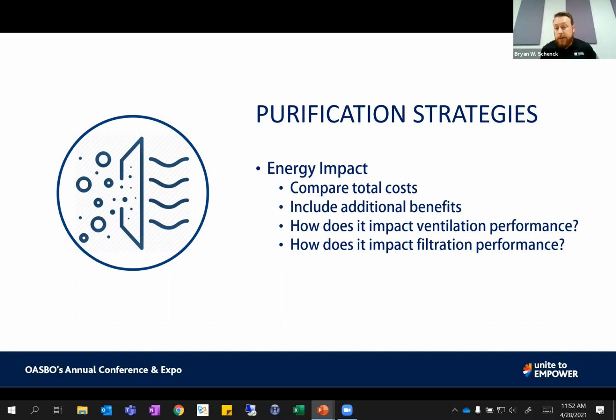Products like ionization are going to make your filtration perform better. It's going to improve your filtration performance. I'll talk about that a little bit when I get there. But ventilation performance now, but also what does the ventilation performance look like for the long term? Products like ionization will actually allow you, because you're cleaning the air, to utilize some of the strategies within ASHRAE Standard 62.1 to reduce the amount of outdoor air you bring in because you're cleaning the air within.